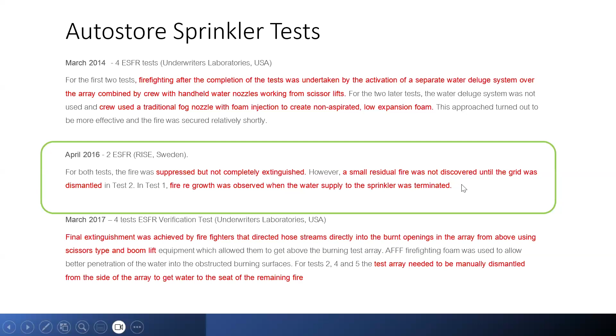Something that I originally missed and went back and reread. Here, a small fire was not discovered until the grid was dismantled. Fire regrowth was observed when the water supply to the sprinkler was terminated. In this test, in their lab conditions, they thought the fire was out and they isolated their sprinklers. And I think that's probably what happened at Ocado, is they thought their fire was out. They thought their sprinklers had done their job because they're looking across the top of the grid. They see fire, then they see water, then they see steam, and they think they're done. But we've seen in the other fire tests that it can be deep-seated and spreading down and spreading sideways. I'm happy for someone to tell me I'm wrong if you have evidence.